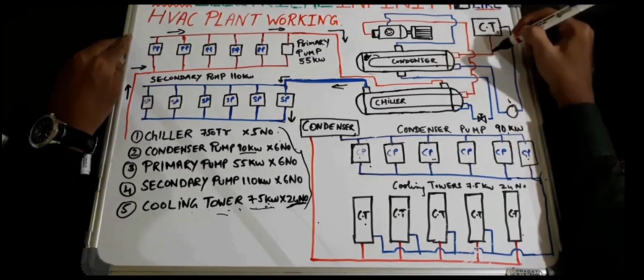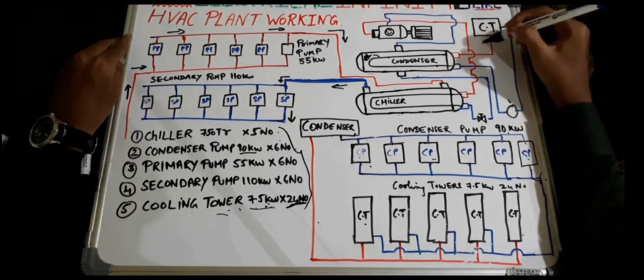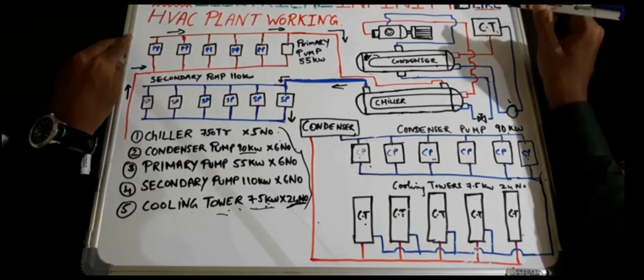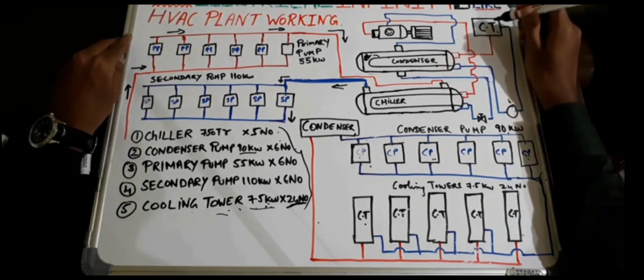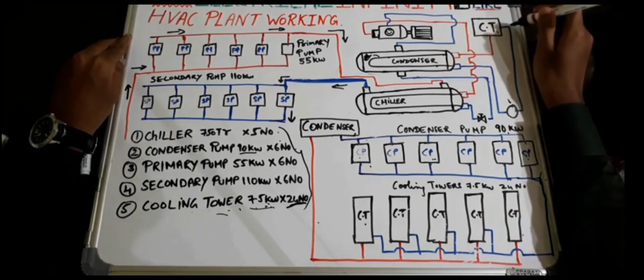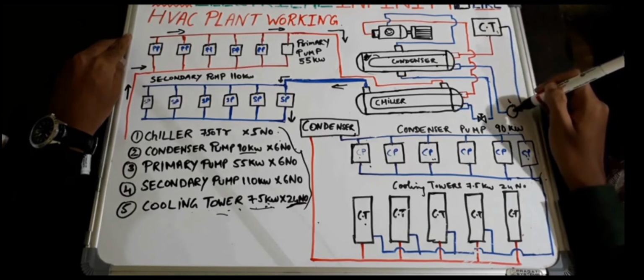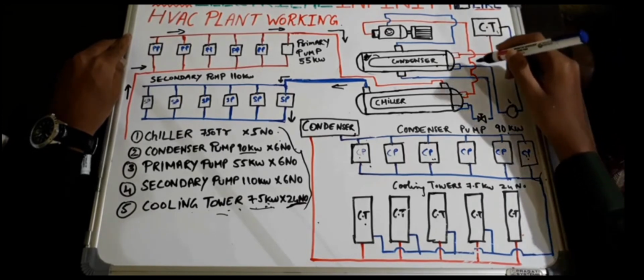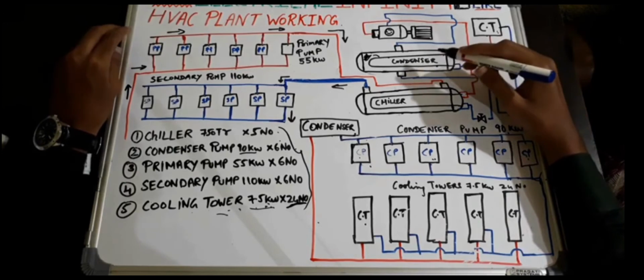As you can see here, this is a red line, and this means the hot water is transferred to this cooling tower for cooling of this hot water. Then again this water is cooled down and sent to this condenser pump, and again the cool water is sent to the condenser for the cooling of refrigerant.